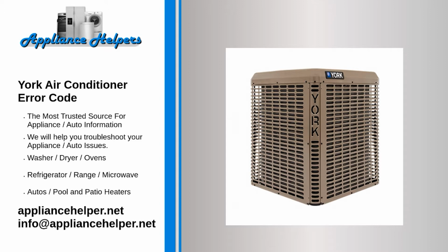Code F1. Problem: Outdoor temperature sensor error. Code F2. Problem: Outdoor condenser pipe sensor error. Code F3. Problem: Discharge air temperature sensor error. Code F4. Problem: Outdoor EEPROM (electrically erasable programmable read-only memory) error. Code F5. Problem: Outdoor fan speed, DC fan motor only, malfunction.